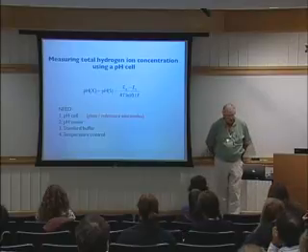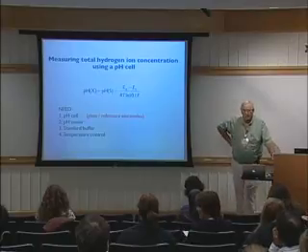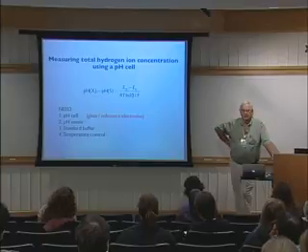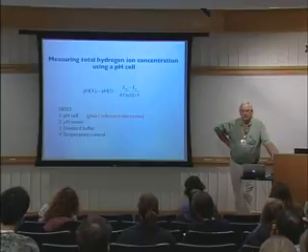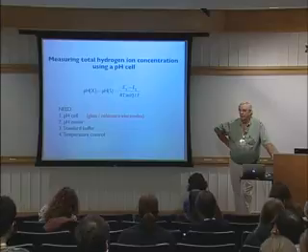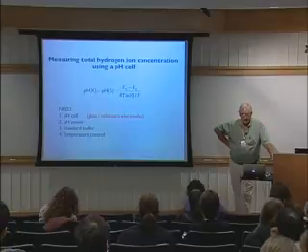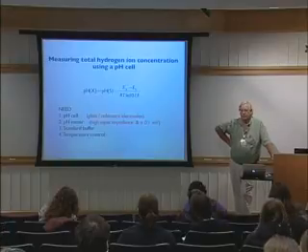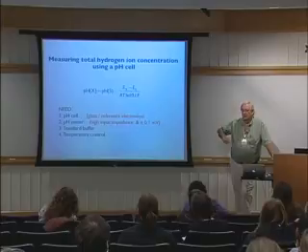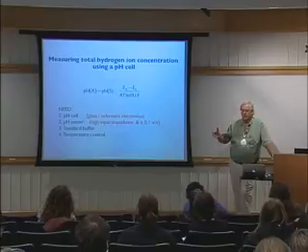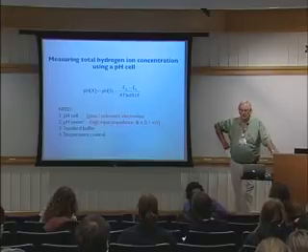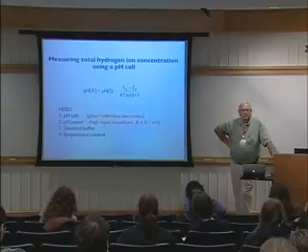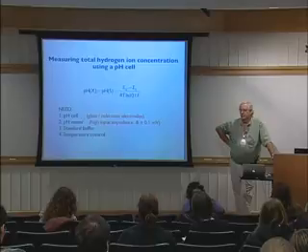So this is a glass reference electrode. Usually, there are other devices out there. Some of them look very hopeful that they will work well. None of them, I think, have been adequately tested. The thing about a pH meter is it's really a voltmeter with a very high input impedance. The glass electrode system, because you've got a piece of glass in your cell, has a resistance of a few hundred million ohms, a few hundred megohms.